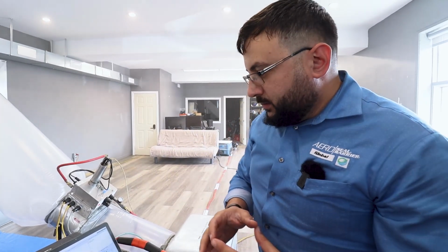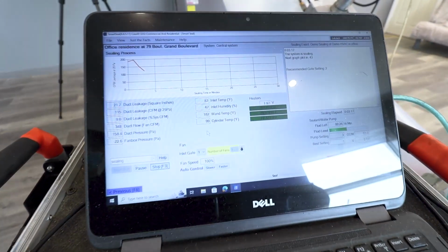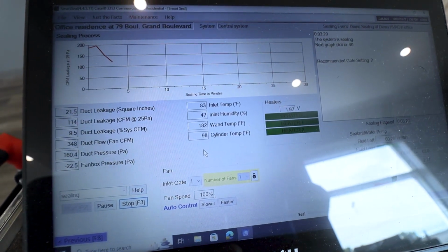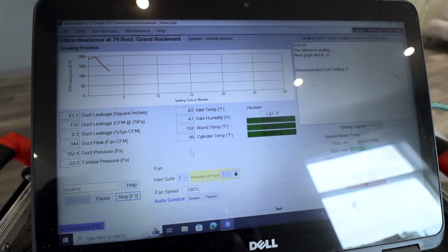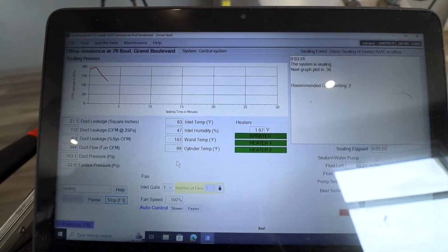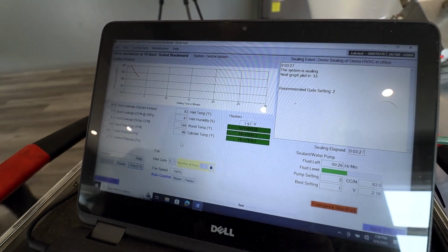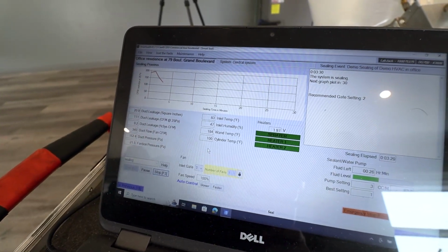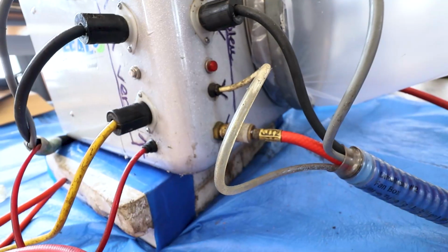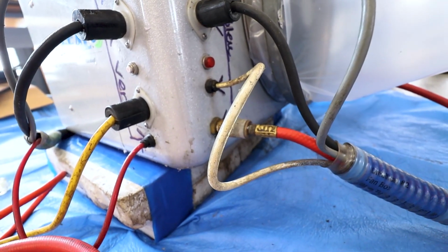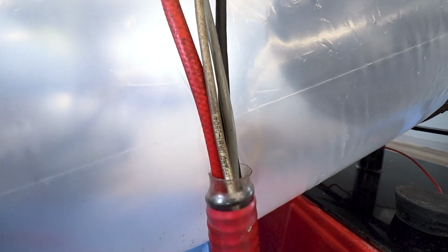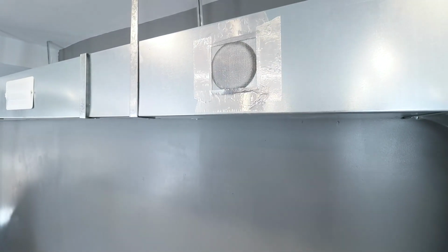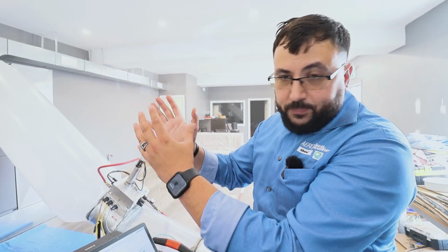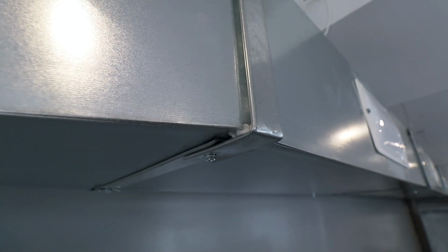So right now during the seal, as we can see, we have our graph over here. We could see already that the air leakage has been sealed in a great proportion. We're at 94% of the system already sealed. That means there's 6% of duct leakage that our computer is showing us. So we're getting to a point where we're making this system as efficient as possible, which can't be done through technicians or a man-made sealing job. So essentially, this is how we're able to go from the inside and catch all the holes.